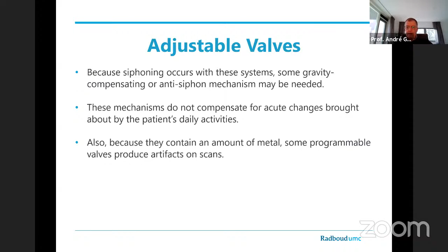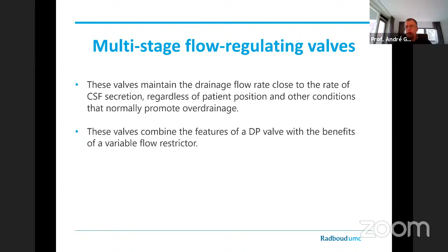There is one type, the Orbis Sigma, the flow-regulating valve. It keeps the CSF flowing through the valve close to the rate of CSF secretion. And it does that regardless of the patient's position, or other positions or coughing that usually promote overdrainage. The problem is that in the normal range of secretion and flow, they simply act not as a variable flow restrictor, but exactly like a differential pressure valve.